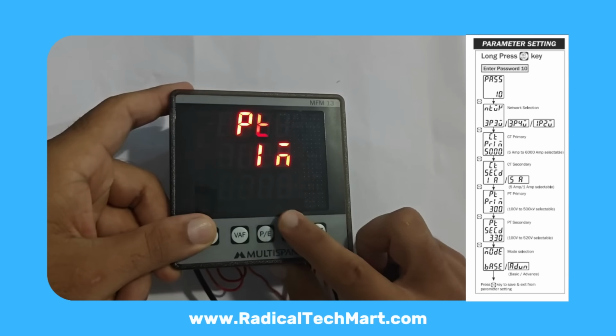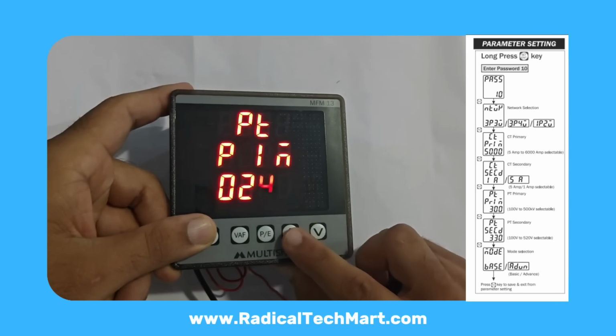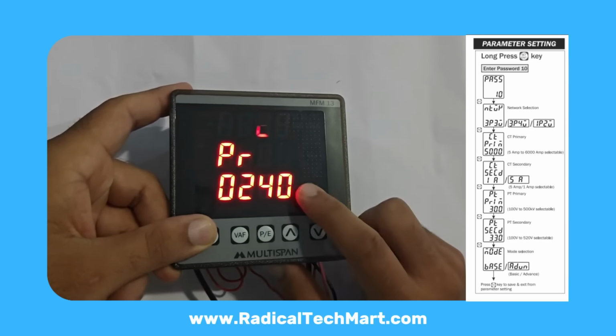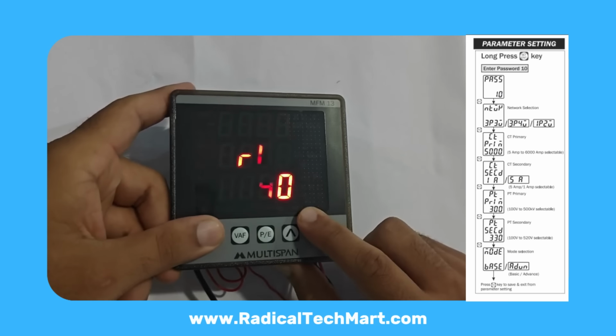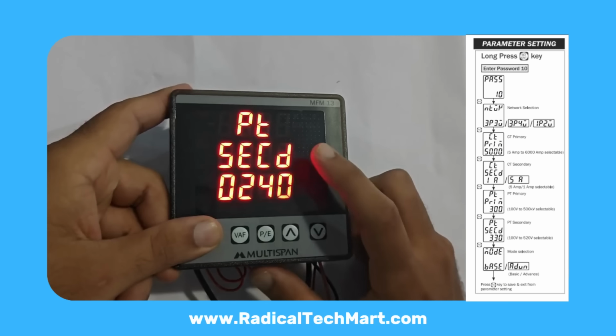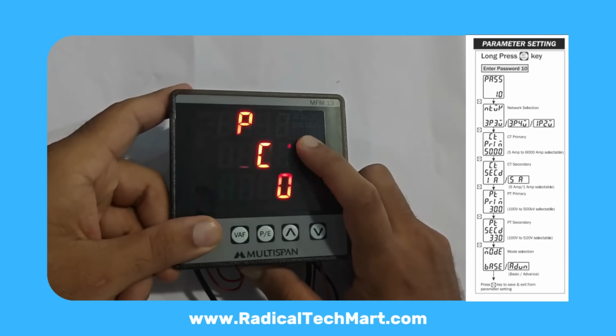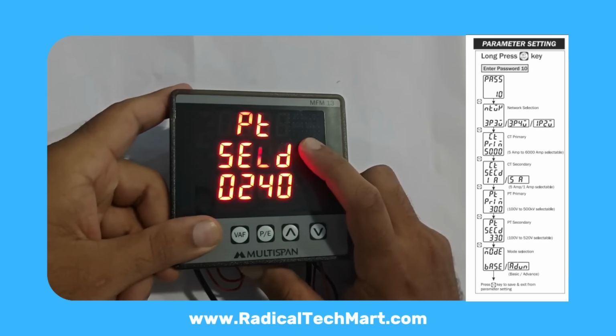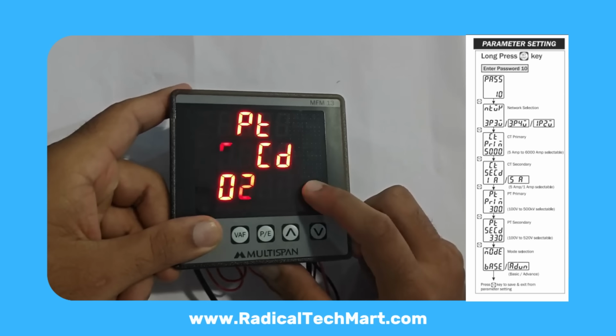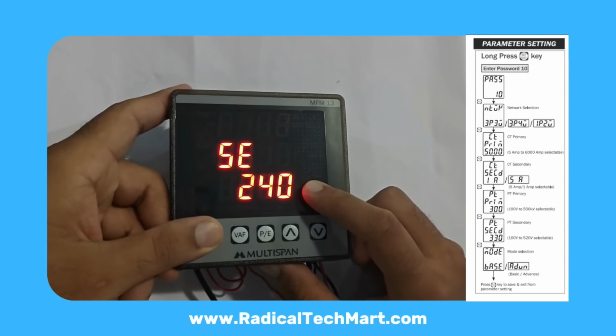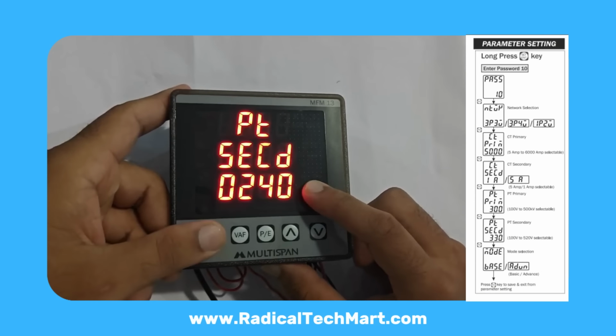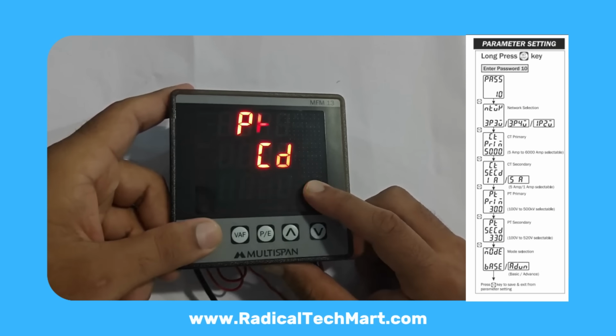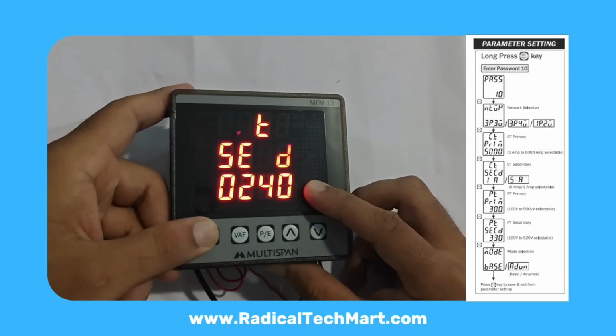Next is PT primary. The default is 0240 volts. If the meter is used on a high tension line, you can set this to values like 11 kilovolts, etc., depending on the PT ratio. Press set again. PT secondary. Here you set the PT secondary voltage according to your PT, example 110 volts, 240 volts, etc.